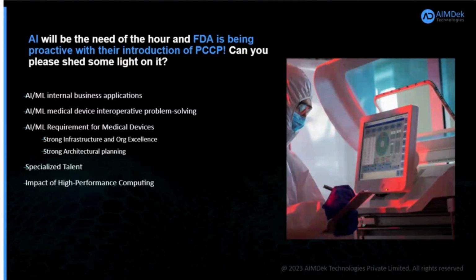PCCP stands for Predetermined Change Control Plan. From an FDA perspective, it is a framework that ensures continuous validation. What's involved in it is a software description, an algorithm change protocol, and a plan for traceability. PCCP is required for manufacturers to present to FDA before the product can be approved. It's a pre-authorization requirement. It also captures a lot about the risk that's distributed within the product architecture. So it's very important to have a very strong architecture and a risk assessment of each element and component of the architecture that may be affected by change.